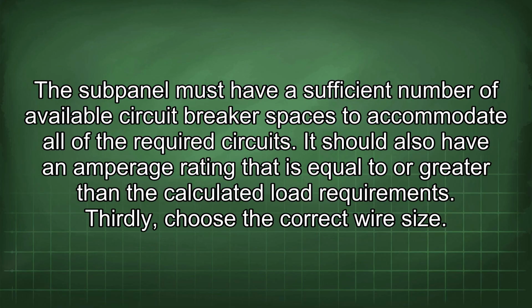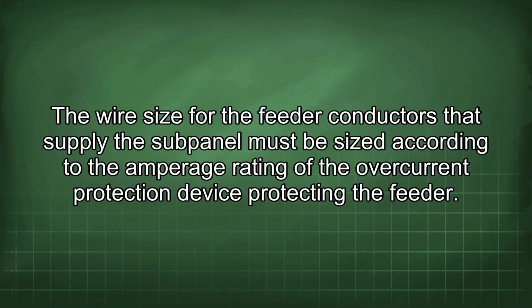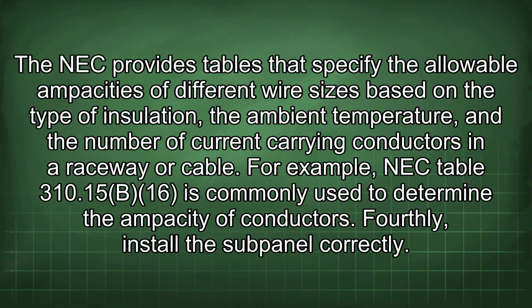Thirdly, choose the correct wire size. The wire size for the feeder conductors that supply the subpanel must be sized according to the amperage rating of the overcurrent protection device protecting the feeder. The NEC provides tables that specify the allowable ampacities of different wire sizes based on the type of insulation, the ambient temperature, and the number of current-carrying conductors in a raceway or cable. For example, NEC Table 310.15(B)(16) is commonly used to determine the ampacity of conductors.